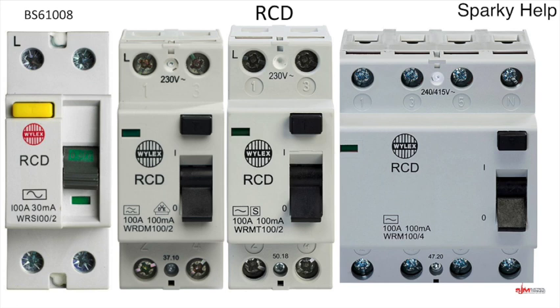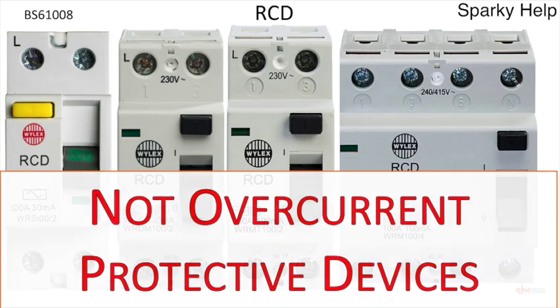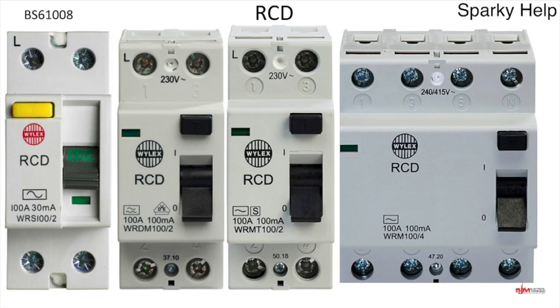Or you could have a four-pole RCD — AC type, 100A, 100mA — so this would be a three-phase and neutral RCD. All of these could be your main switch as shown on the electrical installation certificate. Remember, these are not overcurrent protective devices; they only pick up earth faults or imbalances between the live conductors. These will not disconnect under short circuit or overload situations.